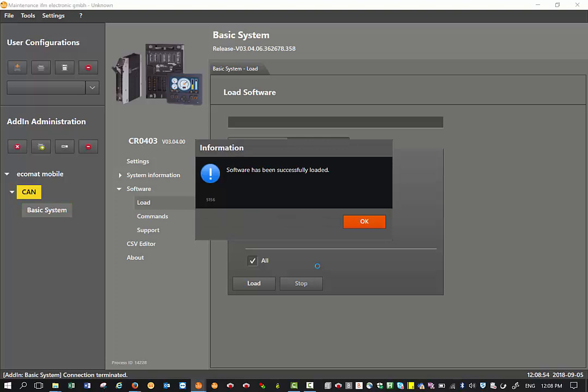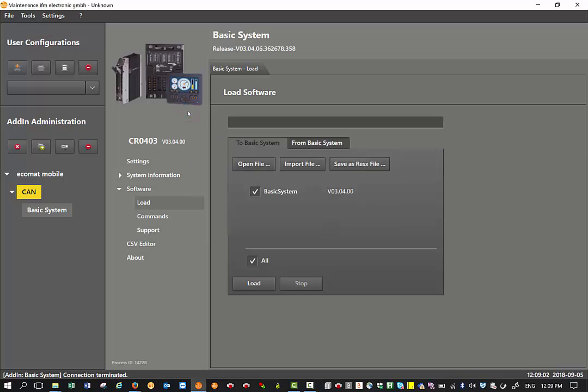Once the software has been successfully loaded, the firmware has been updated on the basic controller. You come up with this message and you can click OK. That means the firmware update has been completed. If you look at the LED on your basic controller, basic display, or the smart controllers, you will see the LED has solid green, which means there's no more application and the firmware has been successfully loaded.